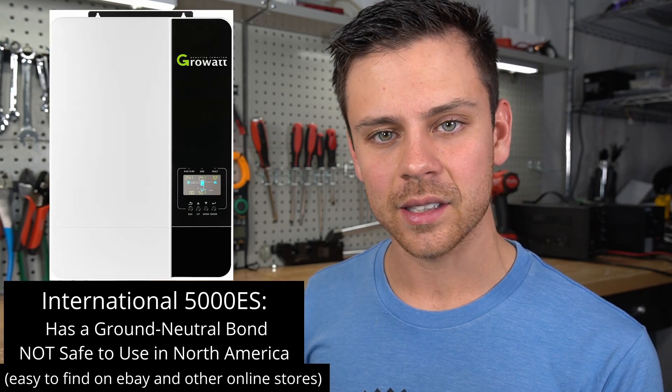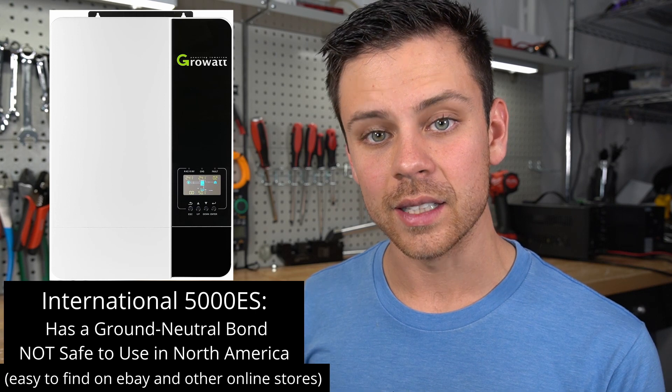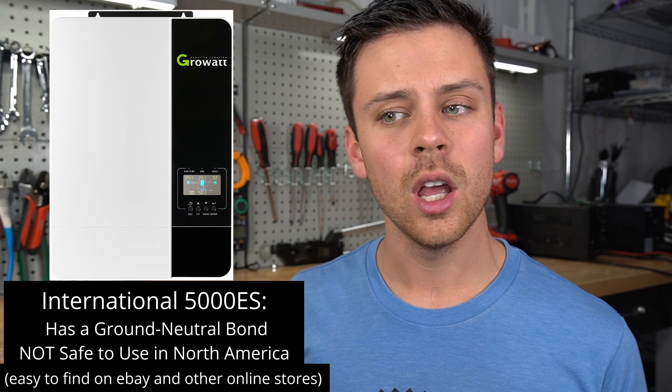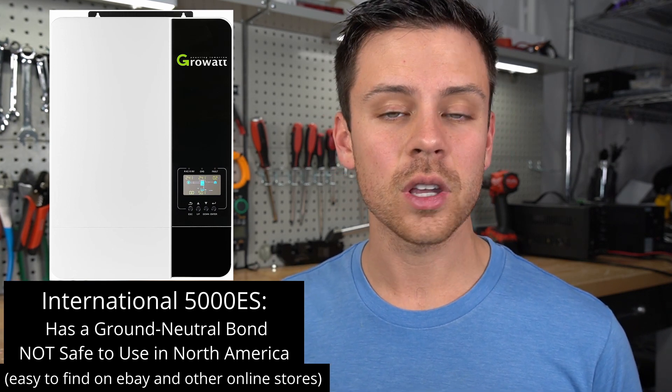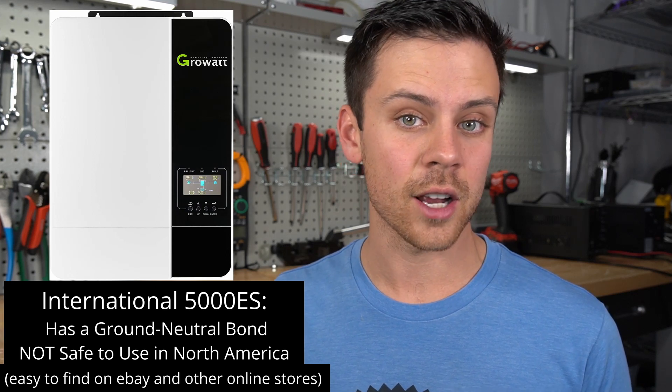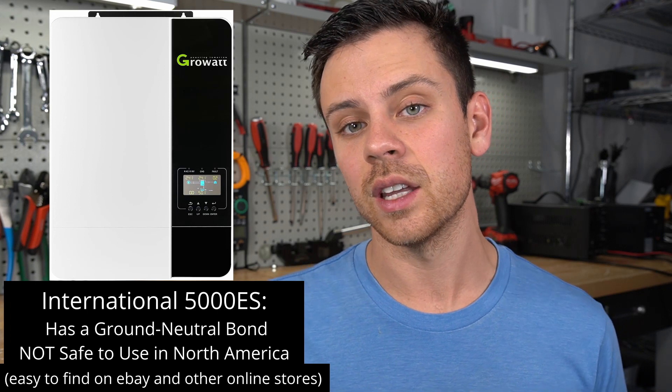Some advanced users are finding ways to use these inverters. The only selling point is that it can be cheaper, but you need to be experienced in wiring it up and know how to ground these inverters properly. They are selling Growatt 5000ES units that have a ground-neutral bond inside the unit. The problem is it has a different designation for ground-neutral when connected to the North American grid, so you could theoretically create 120 volts on the ground of the inverter and shock and kill yourself.